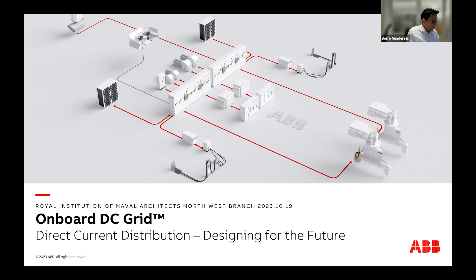Before electrical propulsion came along in the 80s and 90s, many vessels used mechanical systems, and we still have those, but vessels switched to electric with AC-based systems, giving a fixed speed setup fixed to 60 or 50 hertz, so you cannot adjust them. But with DC, you can freely control each individual combustion engine's speed, which gave tremendous savings and better combustion efficiency. That was the main reason at that time.